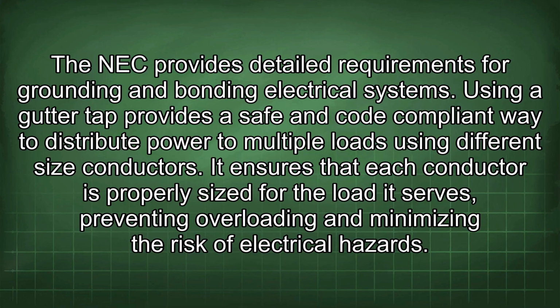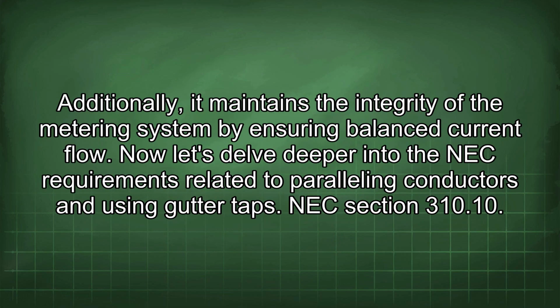Using a gutter tap provides a safe and code-compliant way to distribute power to multiple loads using different size conductors. It ensures that each conductor is properly sized for the load it serves, preventing overloading and minimizing the risk of electrical hazards. Additionally, it maintains the integrity of the metering system by ensuring balanced current flow. Now let's delve deeper into the NEC requirements related to paralleling conductors and using gutter taps.